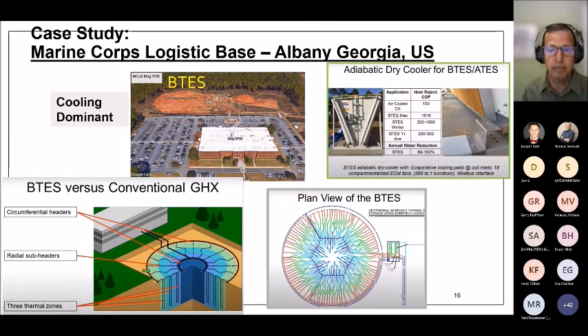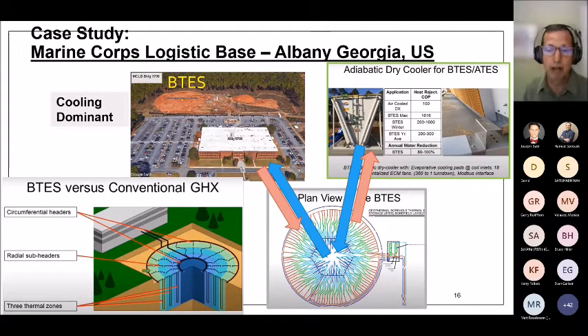Instead of using an electric chiller, they used dry coolers. The way that works is the dry cooler operates when the air temperature is quite a bit cooler than the center of the BTES. It turns on and extracts heat out of the ground, pushes the heat into the air, and returns cooled water back to the center.